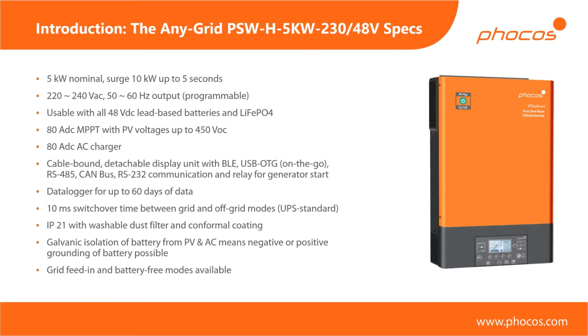We have a very short 10 millisecond switchover time between grid and off-grid modes. So this is almost standard for UPS. It's actually a good standard because if you look at most power supplies for computers, for example, they can handle up to 50 milliseconds typically. So we have a much shorter switchover time here between grid mode and off-grid mode.